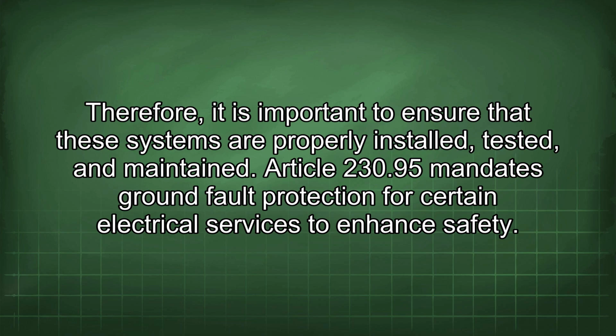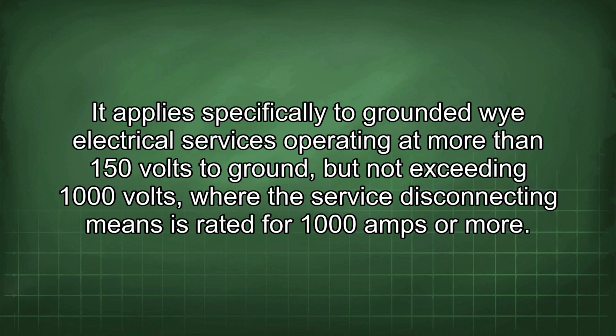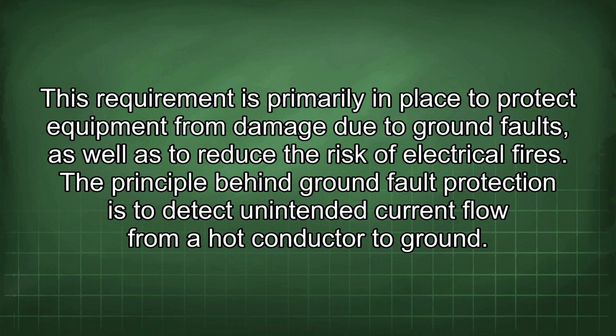Article 230.95 mandates ground fault protection for certain electrical services to enhance safety. It applies specifically to grounded wye electrical services operating at more than 150 volts to ground, but not exceeding 1000 volts, where the service disconnecting means is rated for 1000 amps or more. This requirement is primarily in place to protect equipment from damage due to ground faults, as well as to reduce the risk of electrical fires.